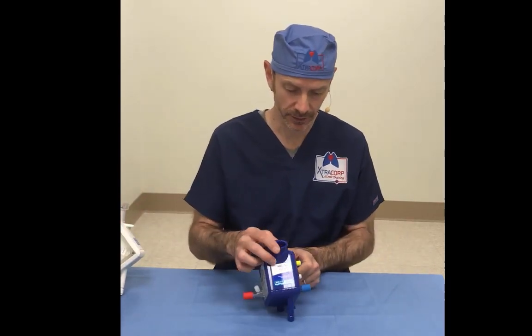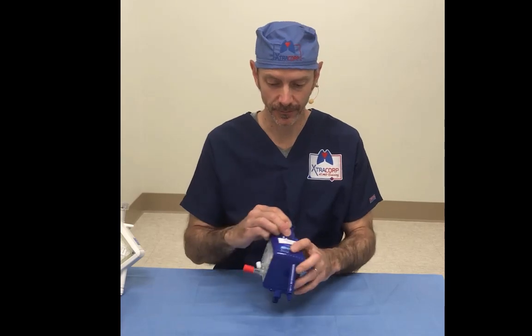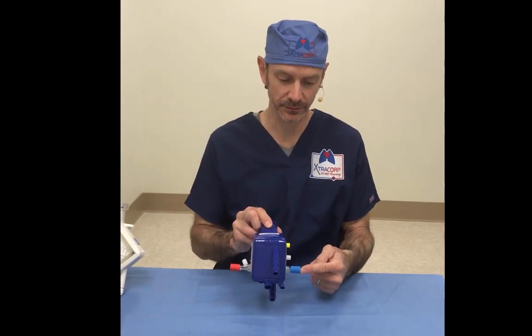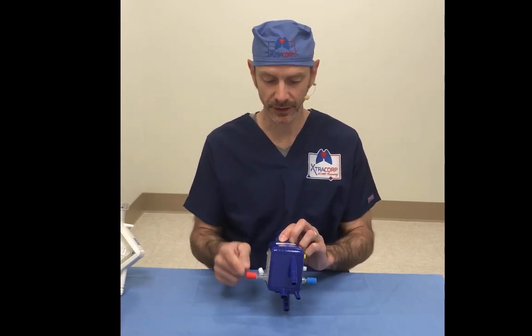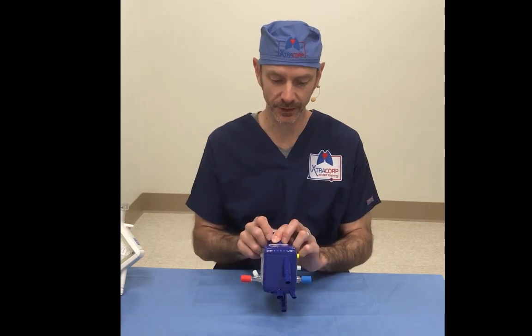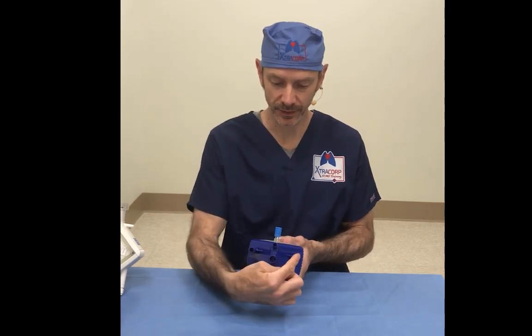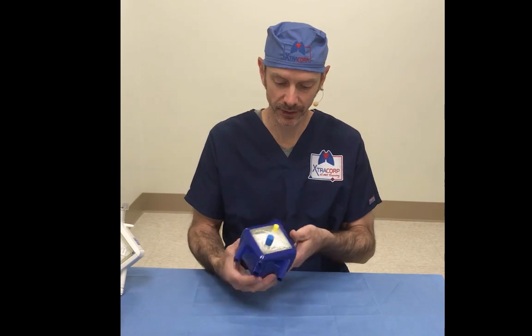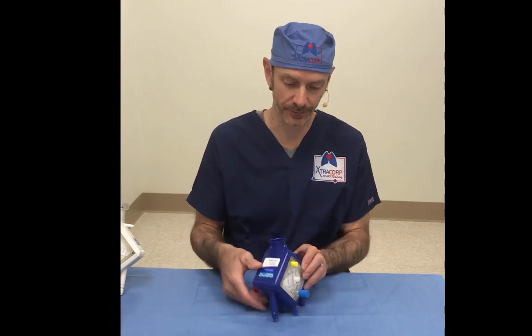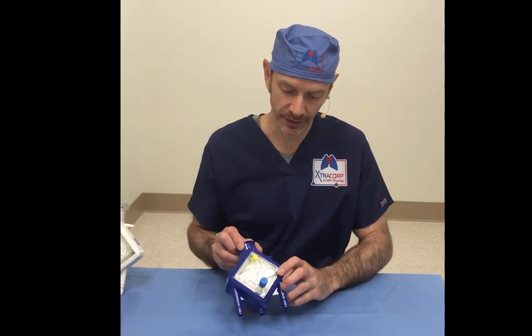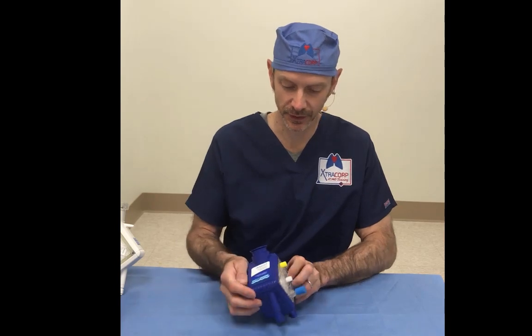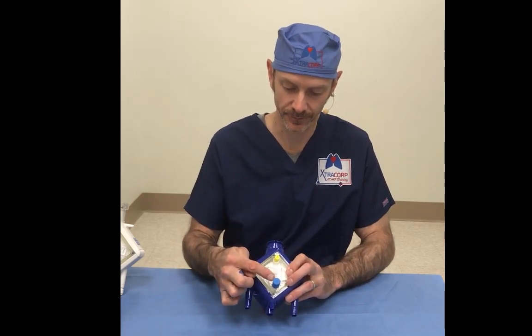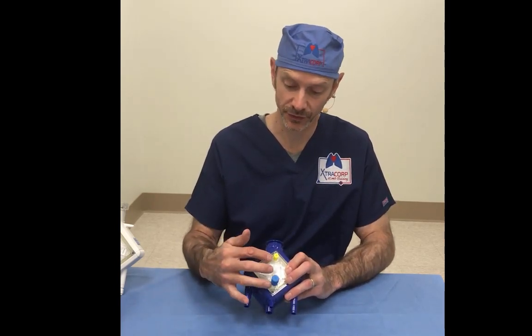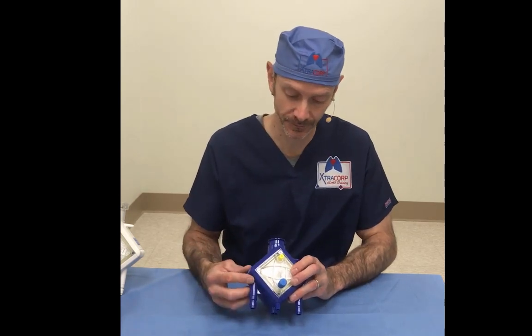We have a pre-membrane side, post-membrane side. Blood comes in, blood goes out. Blue blood goes in, red blood comes out. Water connections on the bottom, gas out on the bottom, gas in on the top. On the pre-membrane side of this pediatric oxygenator, there's 3 connections. On the pre-membrane side, there's 3 connections. I said that twice because it's different than the adult sizes.